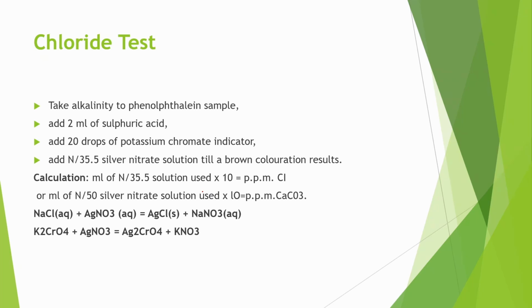Now we have to understand the chloride test. Chloride may be present in the boiler water sample, and it is essential that it be measured, as it would be an indication of salt water leakage into the feed system, either a leaky condenser or primed evaporator.